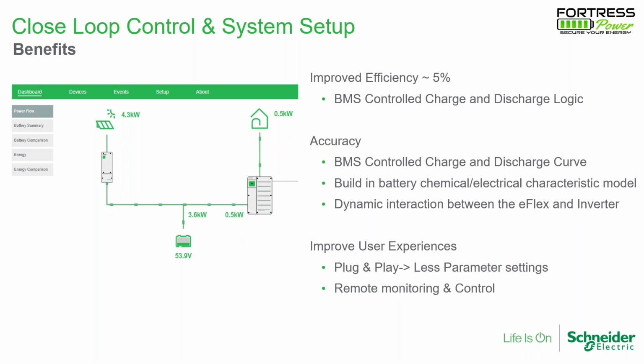In this system, we typically see a 5% efficiency improvement. In open loop communication, we always use a voltage control strategy, which depends on your load and your charge and discharge rate, so you're basically shooting at a moving target. With BMS SOC control, we can improve efficiency by 5% when using lithium batteries.